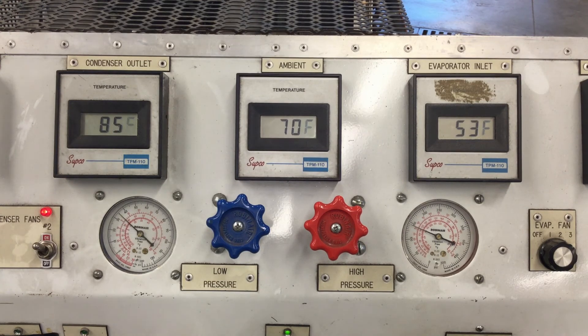Now if you take a look at the cycling, we have a problem. The system turns on for about one second and then turns off. When you first look at this it appears like the earlier situation — just a low heat load cycling — but I want you to pay attention to the behavior more closely.